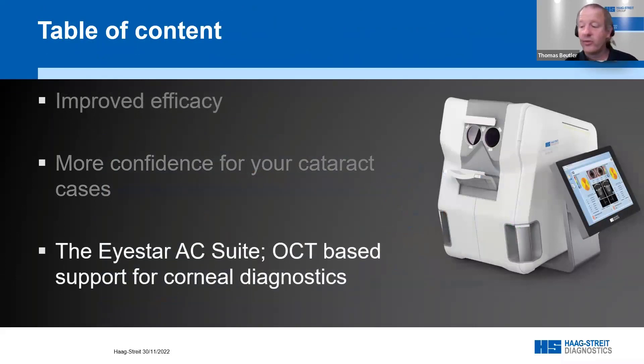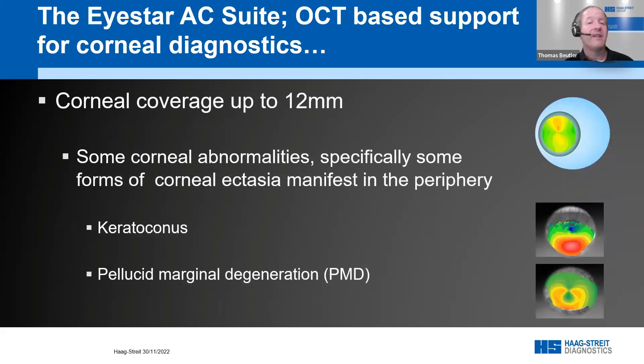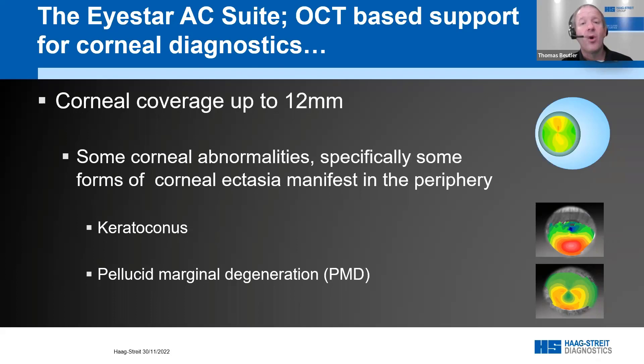The next section is the AC Suite — the OCT-based corneal diagnosis support. With the AC Suite you get extended corneal topography. The cataract suite provides corneal coverage of 7.5 mm, which is suitable for most applications, but in some cases you need more. The AC Suite extends coverage to 12 mm, covering the entire cornea — beneficial for detecting anomalies like keratoconus or pellucid marginal degeneration that occur more peripherally. This extended coverage applies to corneal front, corneal back, and pachymetry.